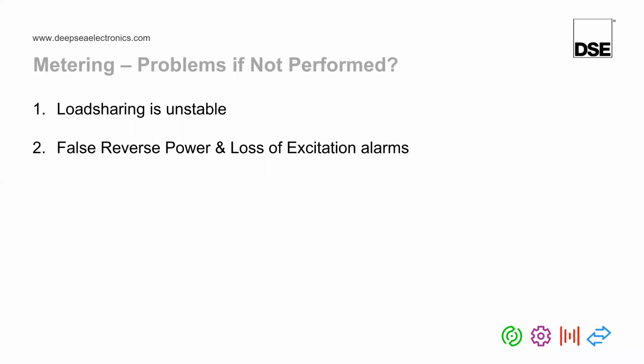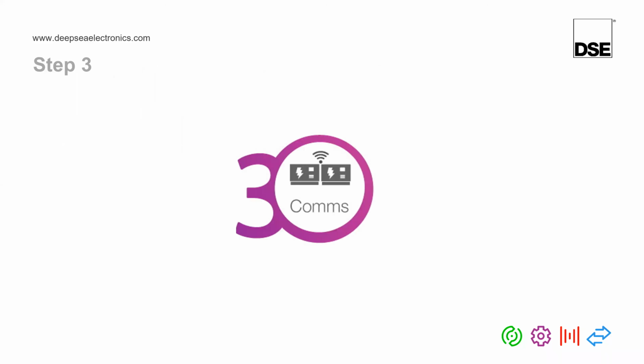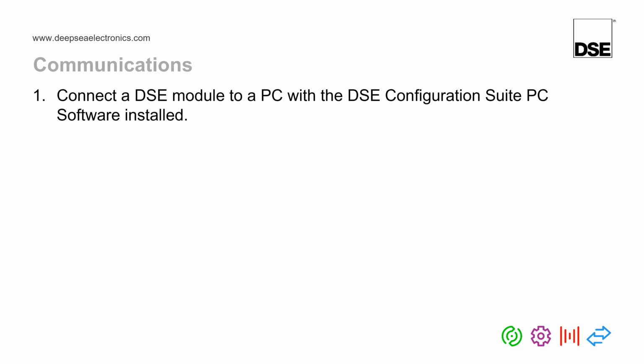Okay, we'll carry on with the presentation now then. We'll go to step number 3. Step number 3 is checking the communications between the two devices, or between multiple modules. And by communication, we're actually referring to the MSC link. MSC, by the way, stands for Multi-Set Communications Link.